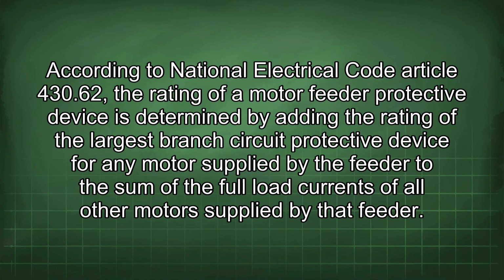According to National Electrical Code Article 430.62, the rating of a motor feeder protective device is determined by adding the rating of the largest branch circuit protective device for any motor supplied by the feeder to the sum of the full load currents of all other motors supplied by that feeder.